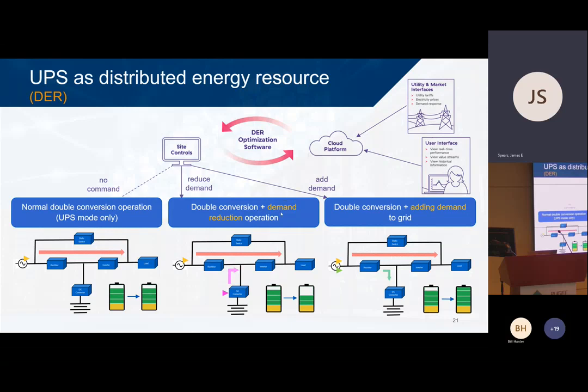So let's say the need is to reduce demand. I want to reduce demand to avoid peak charges, or the grid operator is going to pay me to help them reduce their demand by the use of a large UPS system. Could do this with generators as well. So if I want to perform demand reduction, I want to reduce the incoming power coming into this UPS while still providing all the power necessary for the critical load. So what I do is begin to control my battery discharge, and I don't do a full current, full power discharge, which would only last 5 to 10 minutes. I skim energy off the battery in a controlled fashion, and I can do that for 10 minutes or 30 minutes or 15 seconds or a half hour or an hour.